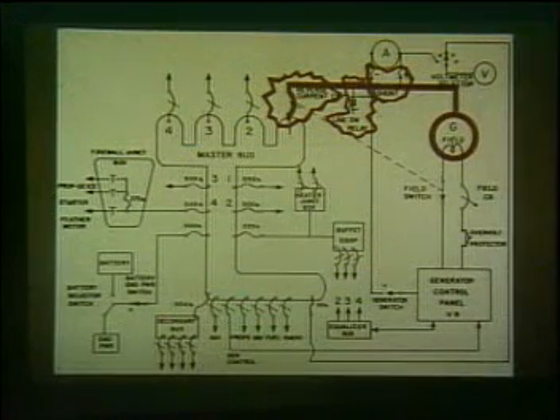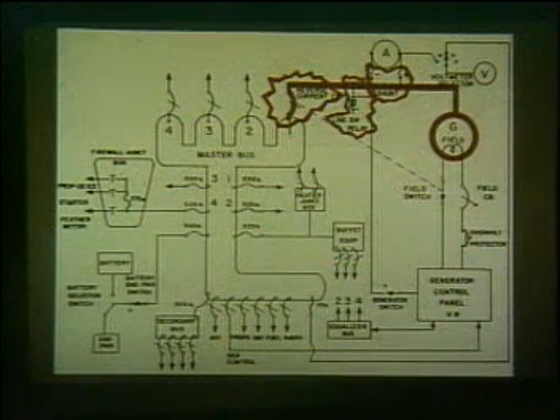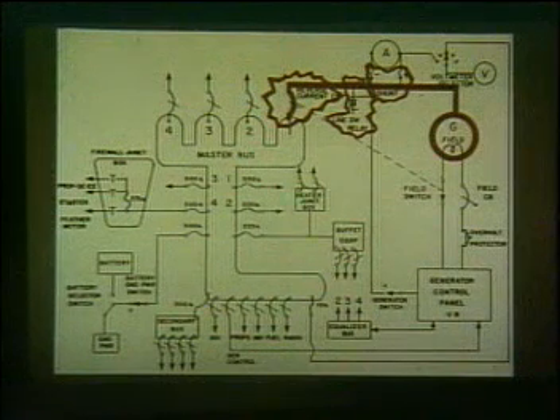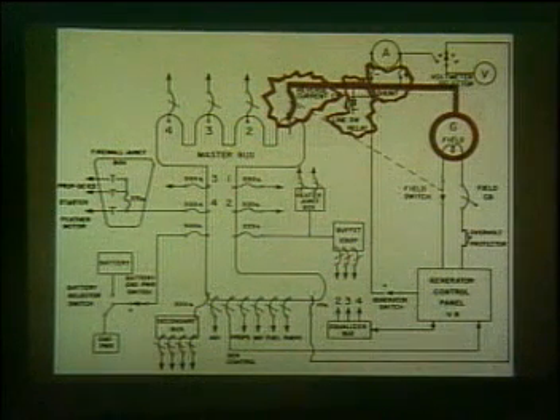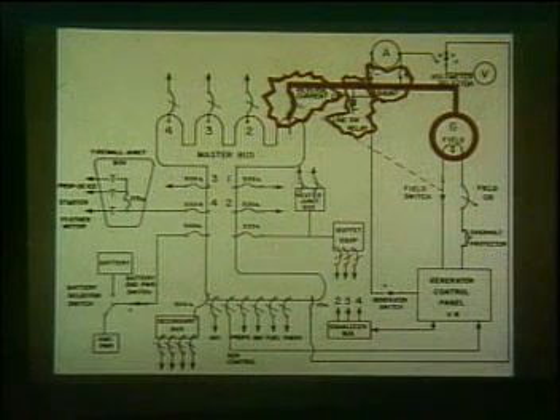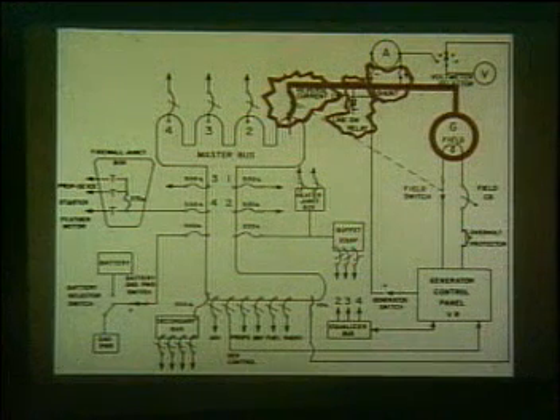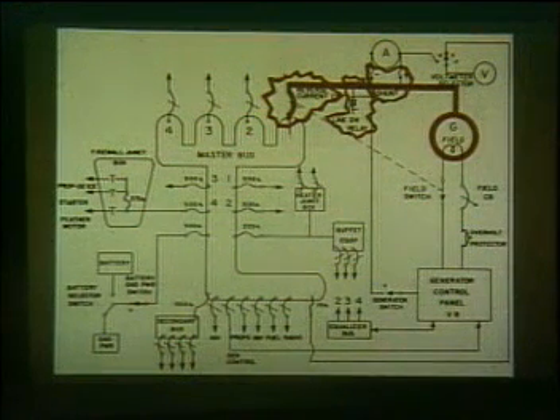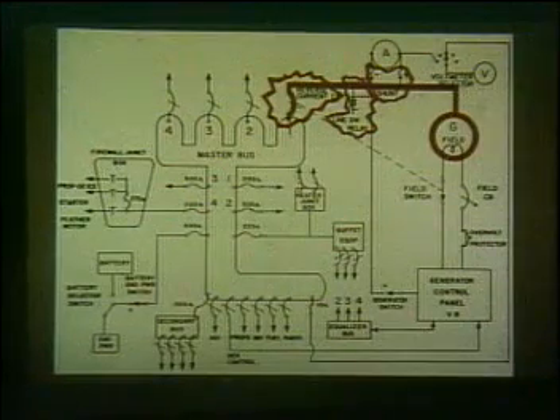Generator output is fed through a heavy feeder cable from the generator to the ammeter shunt in the main junction box. From the ammeter shunt to the line switch relay through a short 8 to 12 inch heavy cable. From the line switch relay over a similar cable to the reverse current circuit breaker. The reverse current circuit breaker is bolted directly to the master bus.